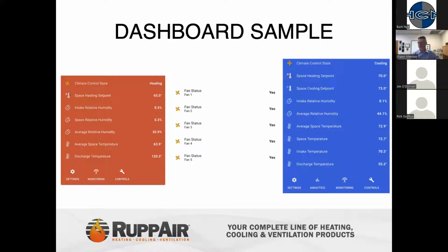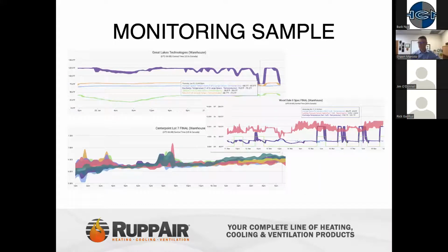Some views of what you'll see from this cloud service, a simple dashboard look at what equipment may be doing, temperatures within the space, humidity that may be in the space, if the unit's in a heating mode red, or if it's in a cooling mode blue, or if it's in idle mode white. Having the ability to monitor these spaces from, again, temperatures through pressure control. And you can see that we utilize this a lot in our diagnosis and troubleshooting.